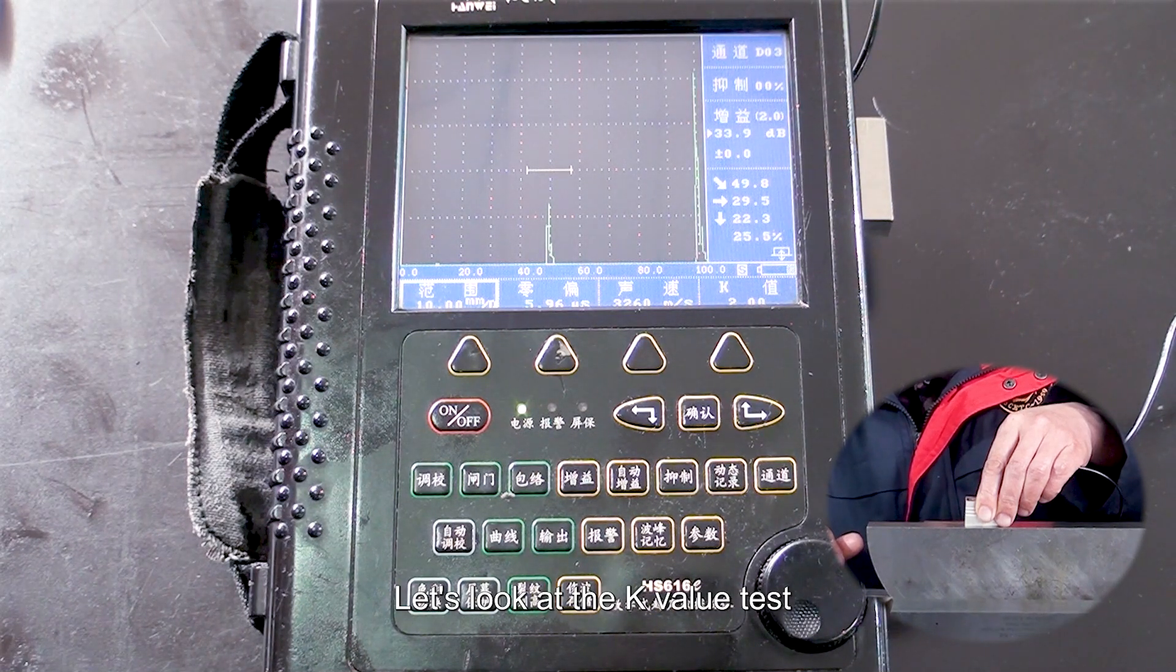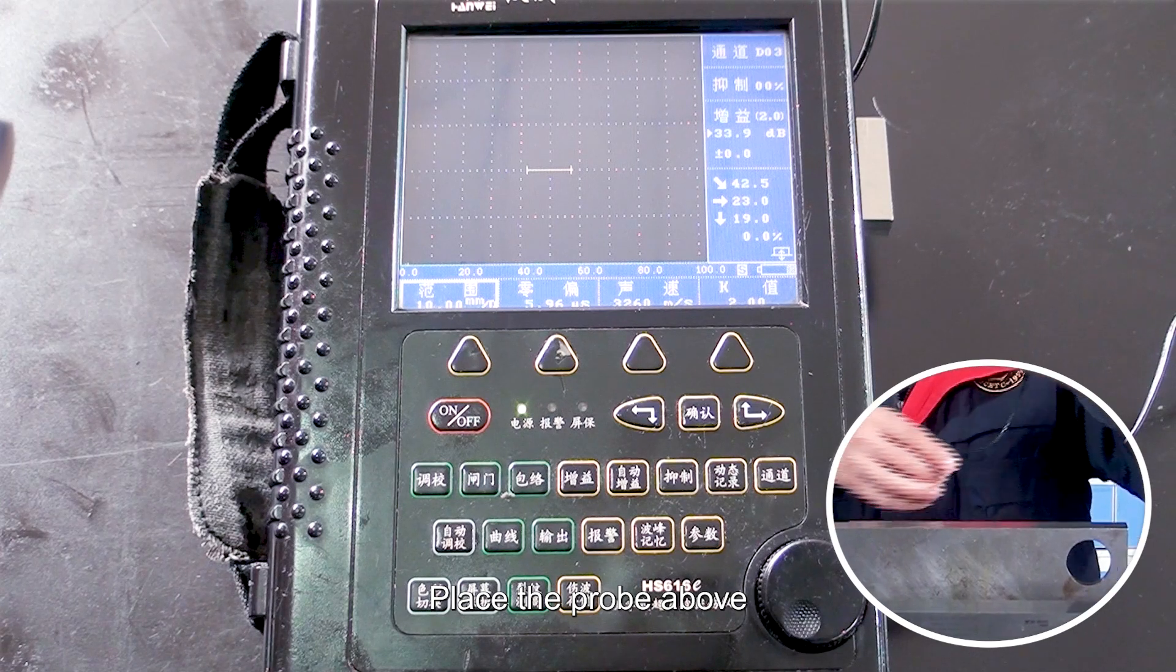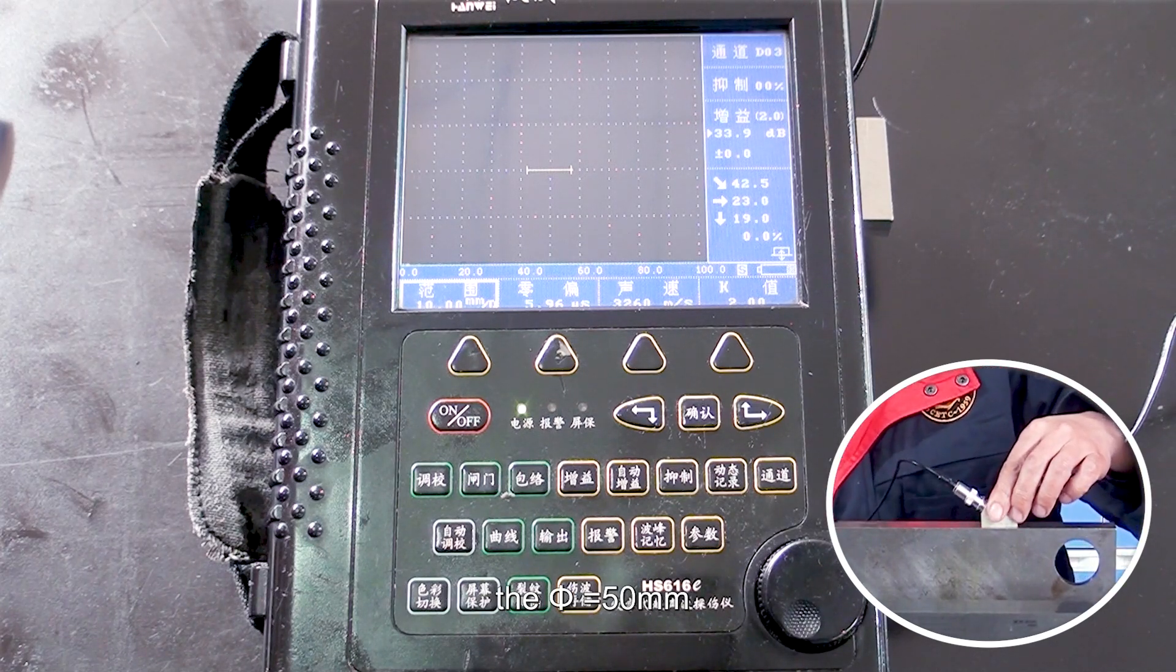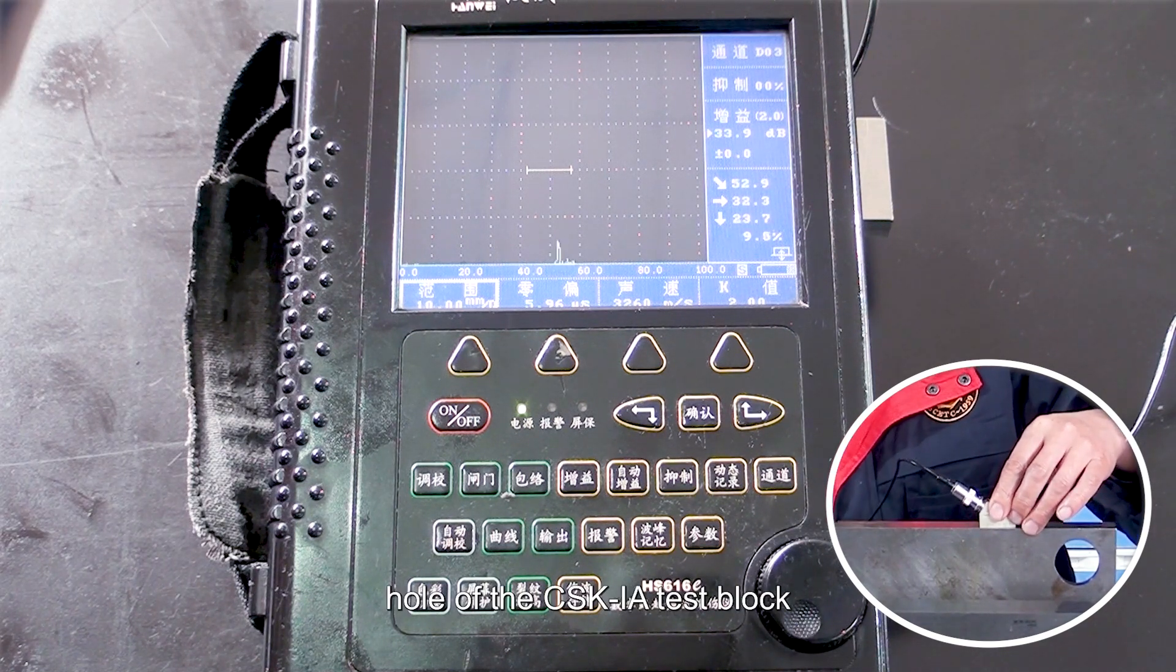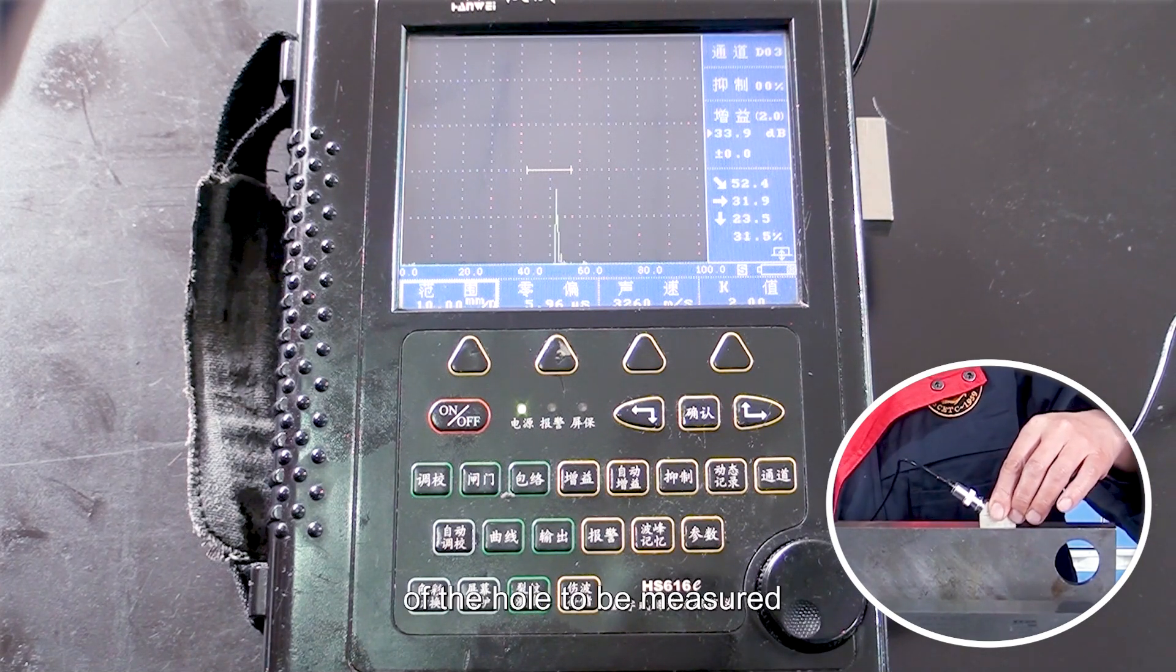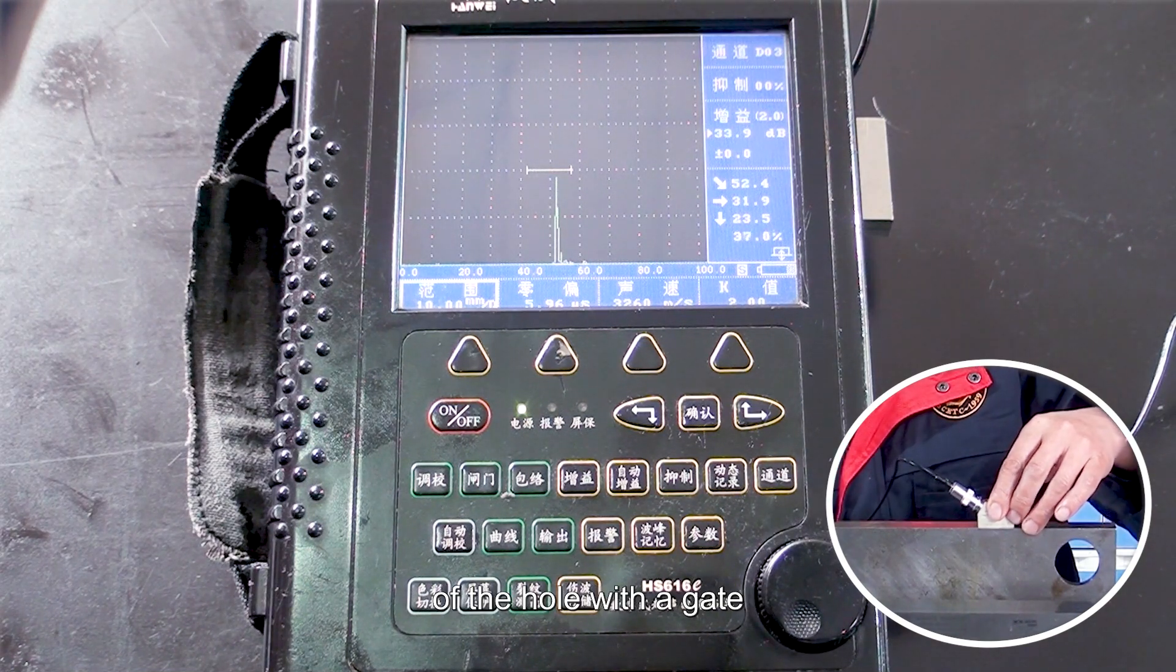Next, let's look at the K-value test. Place the probe above the phi is equal to 50 mm hole of the CSK-IA test block, and find the reflective wave of the hole to be measured.